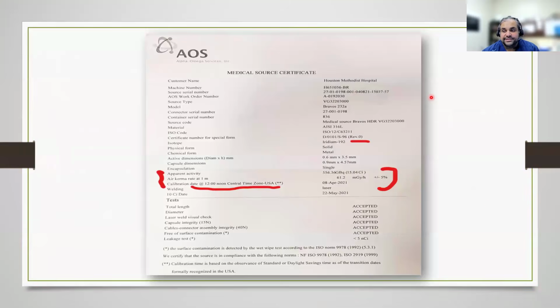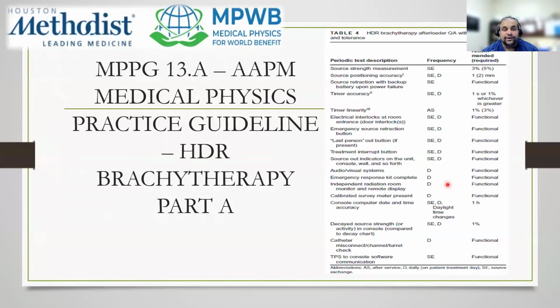So on the day of the source exchange, the engineer will have a source certificate that they will hand over to you. And that document talks about the day the source was manufactured and, more importantly, you'll see the air kerma rate that is provided, which will come in handy when we do our source verification. I do also want to plug the MPPG 13A Part A guideline document that talks about the different tests that you need to do. Part B is more clinical about different types of treatments. Again, you can look at it, and it has a lot of helpful tips and also the frequency of the tests and the tolerance levels that are provided.